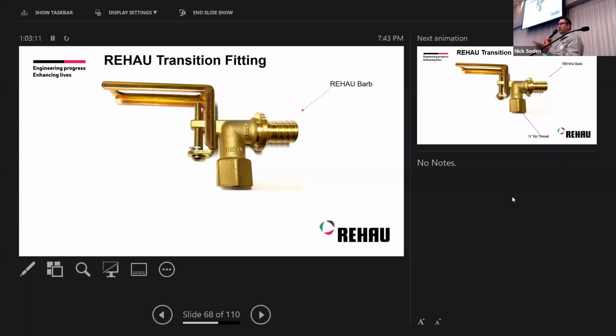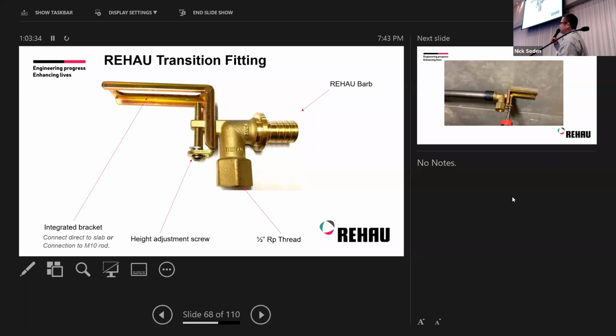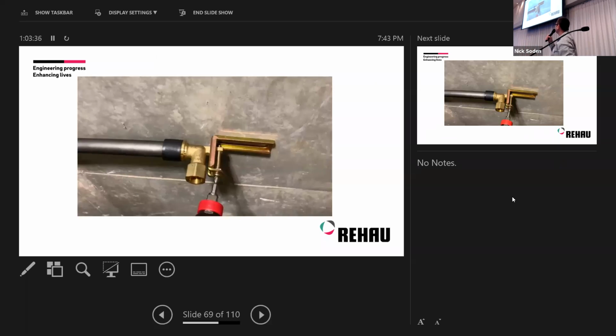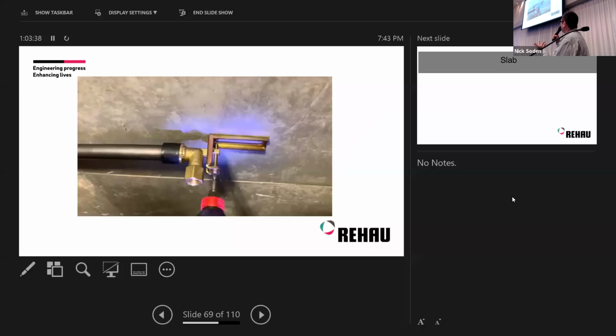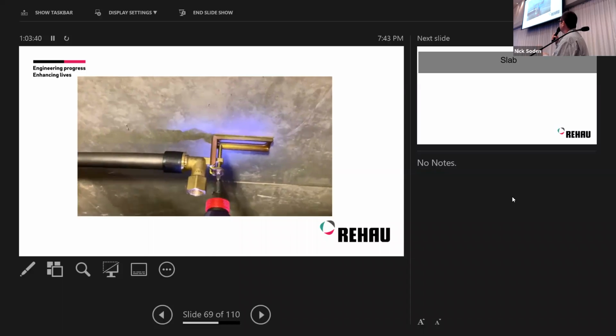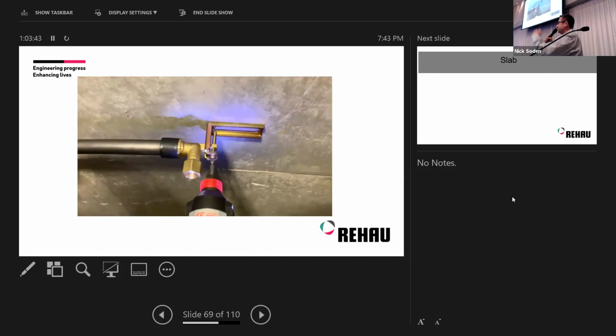Although traditionally Rehau is known a lot for their 16 and 20, which is for your apartments and your housing, etc., in this application it's 25mm and above. It's got a 1/2 inch thread for your sprinklers. It's got an integrated bracket, which can be connected directly to the slab or via an M10 rod. And it's got the height adjustment screw, which, like I said, is within the escutcheon plate. I'll show you. This is basically how it works in operation. Just a Phillips head to go up and down, okay?